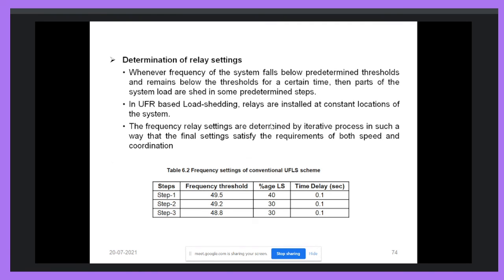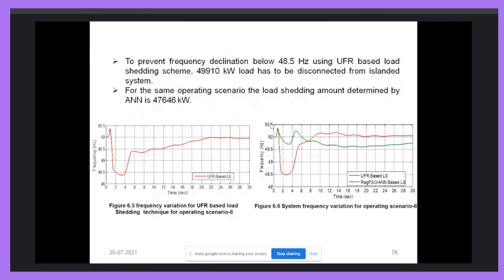In a particular step, we have to define a particular value of the frequency. Suppose when the frequency reaches 49.5 hertz, then the first step will be activated and 40% of the load will be disconnected. Whenever the frequency reaches 49.2 hertz, step 2 will be activated and 30% of the load will be disconnected from the system. Similarly, for step 3, when the frequency reaches 48.8 hertz, the third step will be activated and the load will be disconnected. Here you can see the comparison.